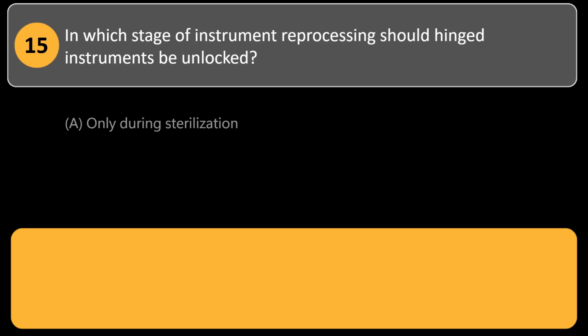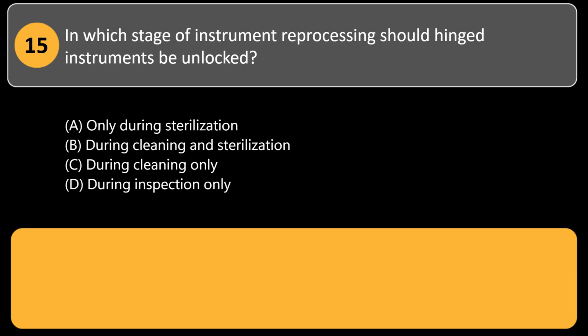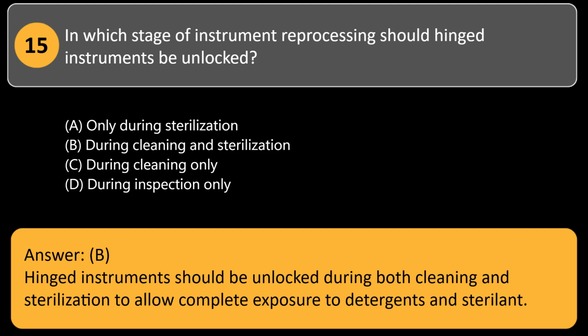In which stage of instrument reprocessing should hinged instruments be unlocked? A. Only during sterilization. B. During cleaning and sterilization. C. During cleaning only. D. During inspection only. Answer: B. Hinged instruments should be unlocked during both cleaning and sterilization to allow complete exposure to detergents and sterilant.